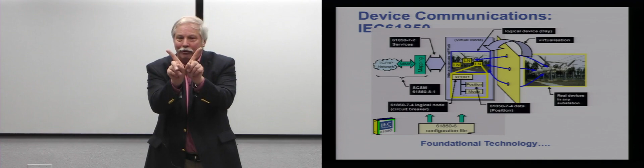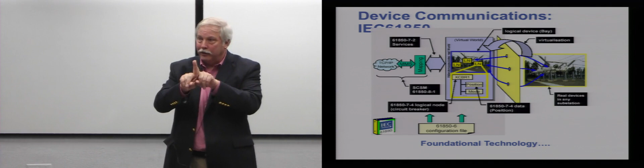If I close when the angles are 180 degrees apart, what do I get? A short circuit, because the voltages are literally opposite one another. So where do I want to close? At zero. I want to look at the angles in real time and make sure that when the angles are aligned, I issue the reclose function.